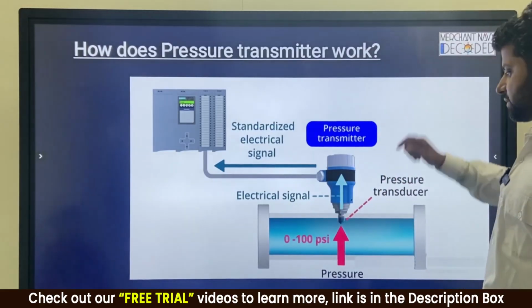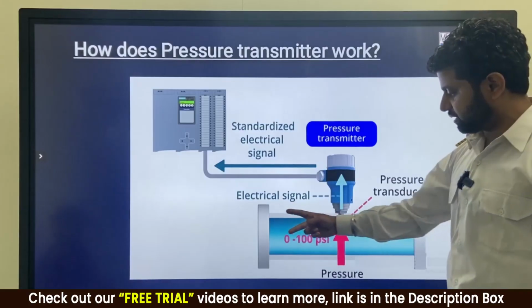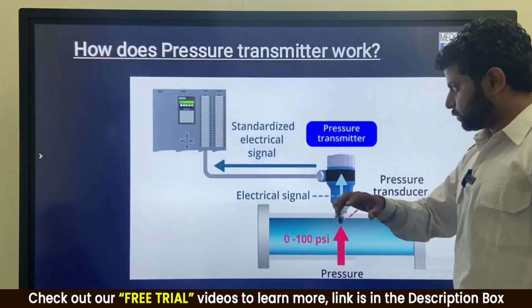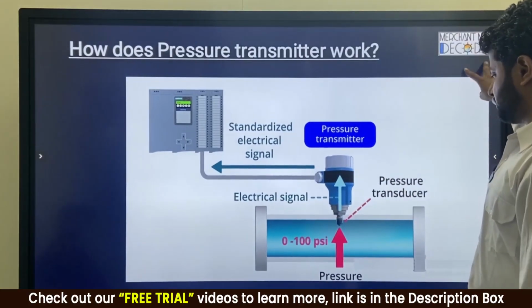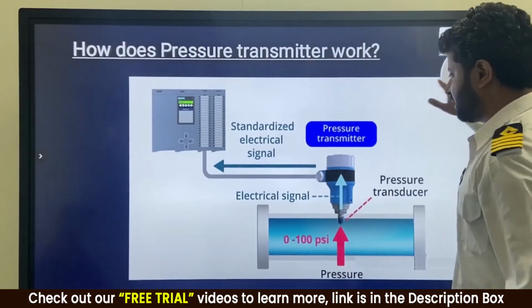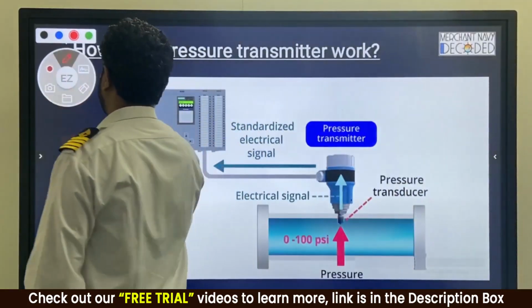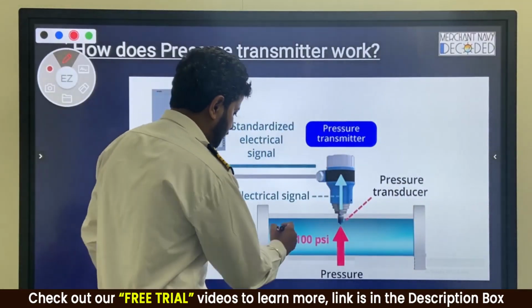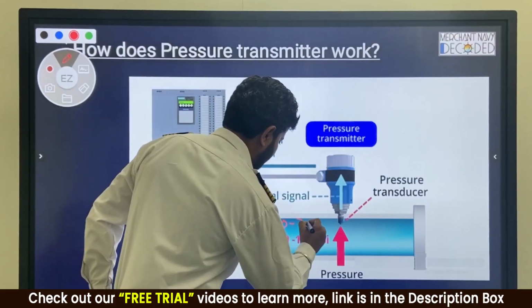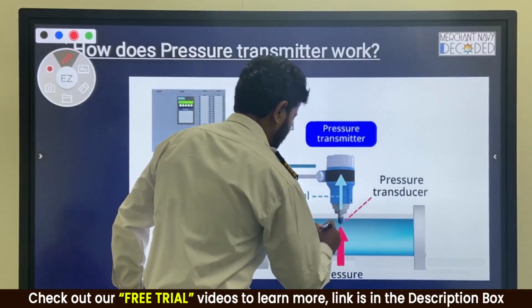Let's see how a pressure transmitter works. So this is a pressure line in which water is flowing and it has a 0 to 100 psi value, which reminds me, 100 psi is 6.9 bar, so 0 to 7 bar is its value. Here the pressure comes, 0 to 7 bar.